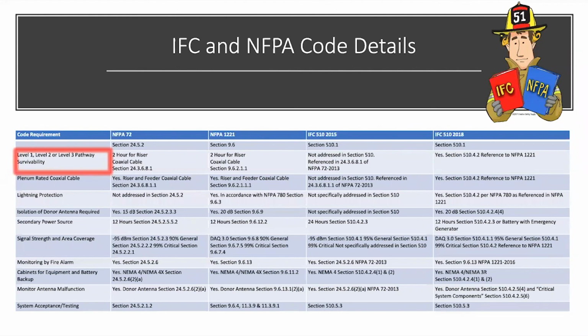Typically, we use 2-hour rated pathways in these systems. Plenum rated coaxial cable is required. This means that the cable meets an NFPA standard certifying that it won't release toxic gases if exposed to fire. Any outdoor antennas must have additional protection against lightning strikes. This is for protection of the electronics equipment connected to those antennas.